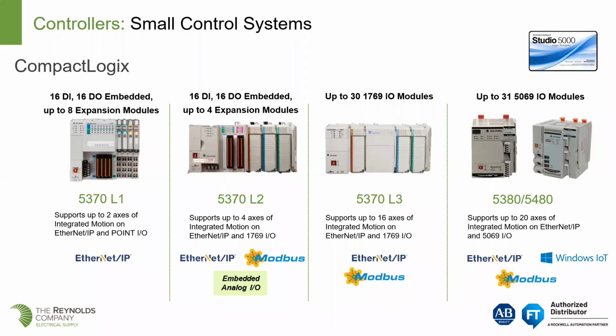We need all of our customers to understand that, because not all of the new IO that's being released today, and I'll talk about this later, can work with every controller. A lot of the newer IO will not work with the 5370 type controller. You have to use something that has a quad core processor. Yep. Mike will cover the IO here in just a few moments.